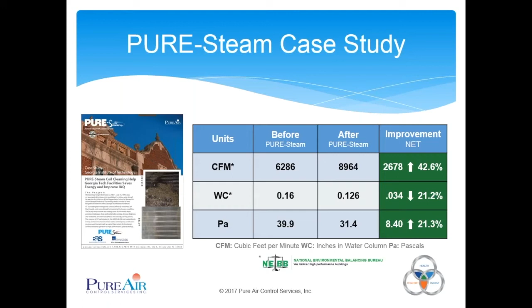So, much like USF, we've been doing ongoing work up at Georgia Tech. Georgia Tech is committed to sustainability. They've been conducting experiments in various different parts of building engineering and balancing. And so when we came in to clean their coils, they wanted to take that opportunity to test on their own to see what kind of results they got. So yeah, as you were saying, Frank, that's absolutely true. The NEBB saw a 42.6% increase in CFMs and a 21.2% net improvement with the inches in the water column. And also a significant Pascal improvement as well, you see on the bottom column. And that was numbers that we took from our coil cleanliness verification test, our CCVT test. That's correct.